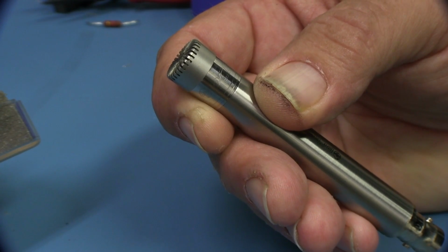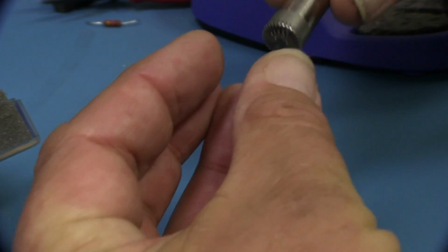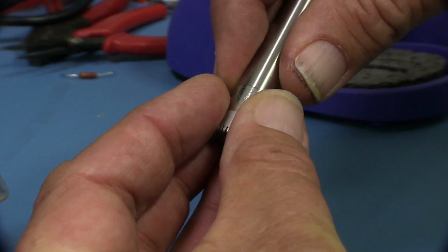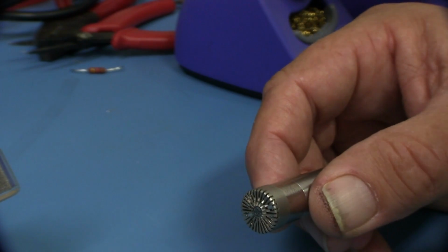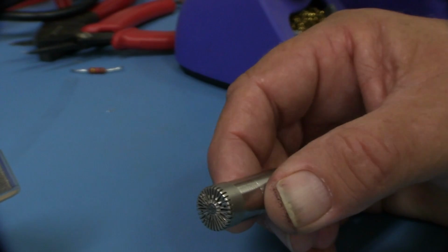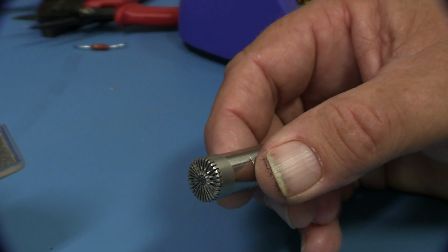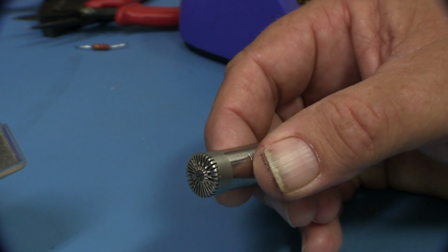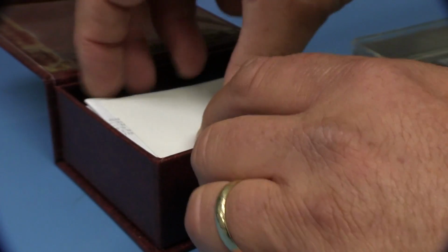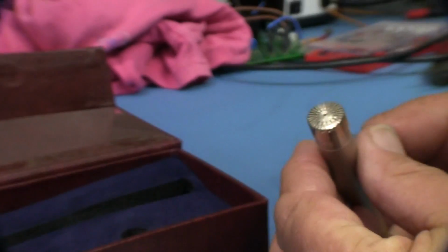How do you couple in that generator to it? Is it a set distance away, or is it inside a cavity? It's inside a cavity. It actually push fits into it. It's a push fit, right. Yes, so it's sealed in there. Got it. And the calibrator itself has internal feedback and its own internal servo system to maintain consistent pressure inside that cavity. Secondary microphones are basically almost identical, except that these ones here, they really are awfully similar.